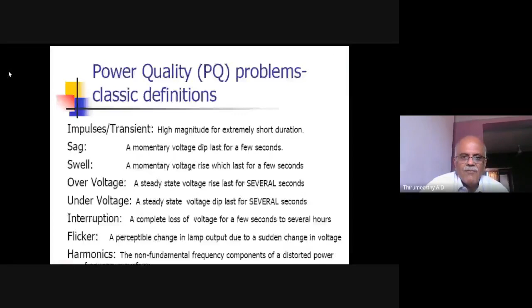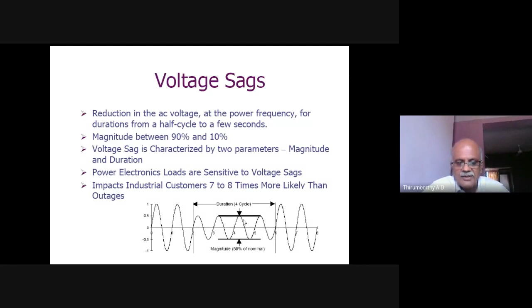So during those 200 milliseconds, these healthy feeders will see a low voltage condition for 200 to 300 milliseconds. So this is actually the voltage sag, and the equipment connected in all these feeders will react to this condition, and mostly variable frequency drives will get tripped. You can see that 10 to 20 years back, for example, in a textile mill, everybody will be using sturdy induction motors. But nowadays, for the requirement of variable speeds, for automation, and also for energy efficiency, people go for variable frequency drives. But in these voltage sag conditions, these variable frequency drives will get restarted or tripped.